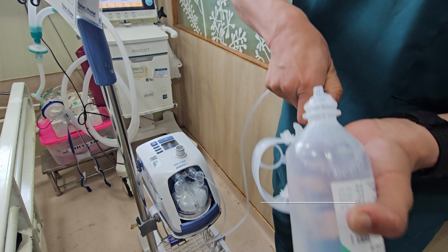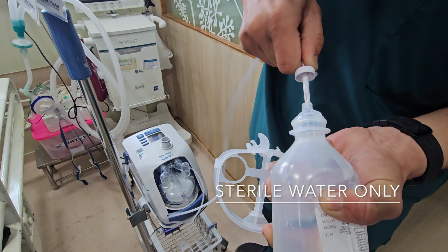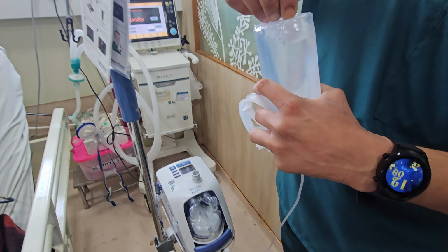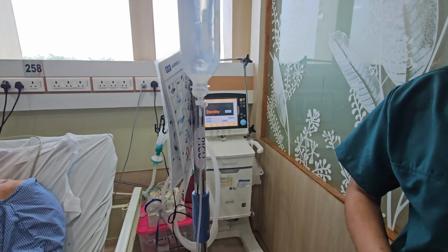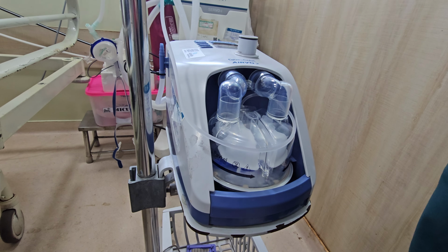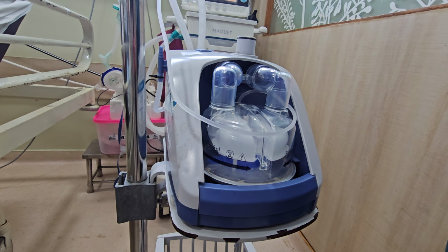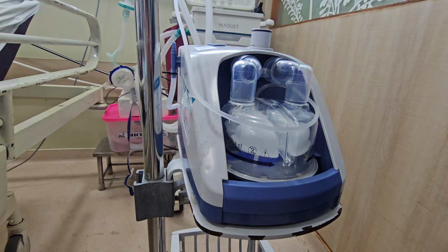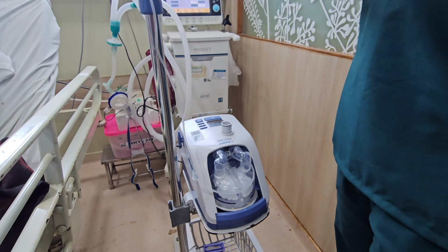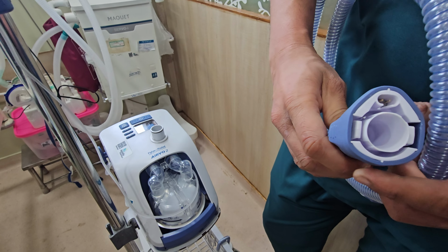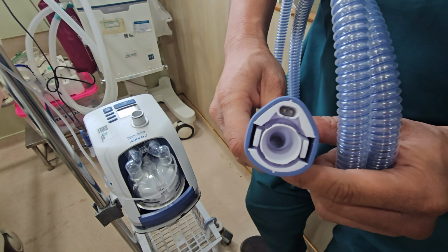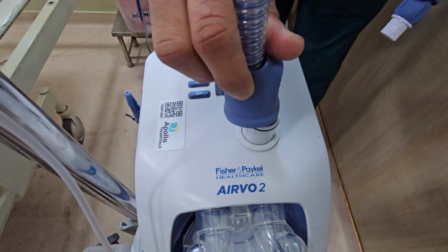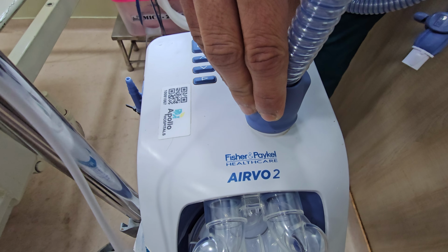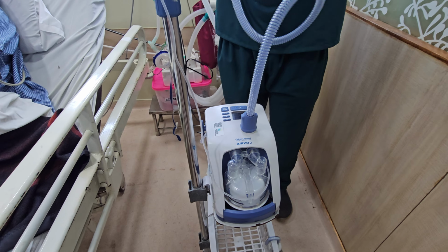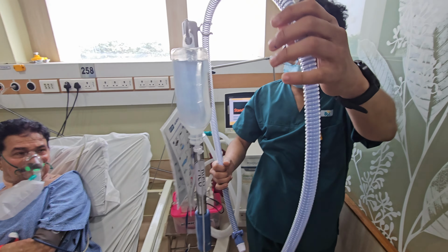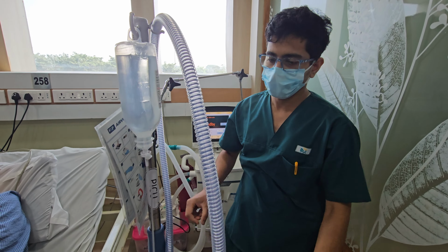For humidification, only use sterile water. The bottle spiked with the connecting tube. And water filled up to the mark in the water chamber. Connect the AIRVO flow tubing to the machine. Now it's ready to use. We need to set the parameters.